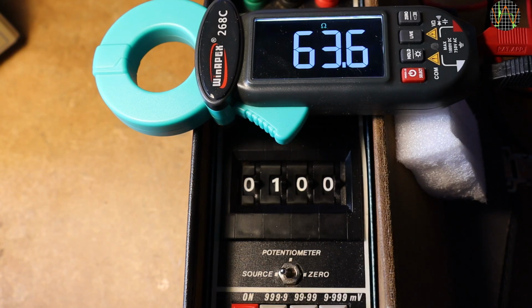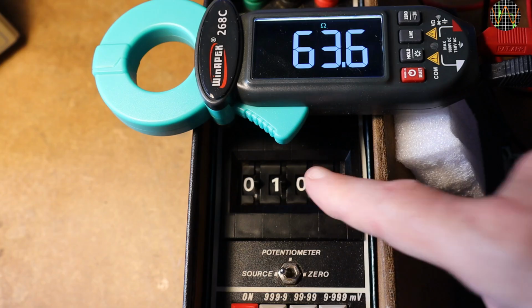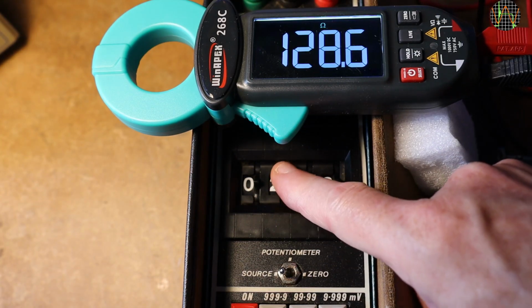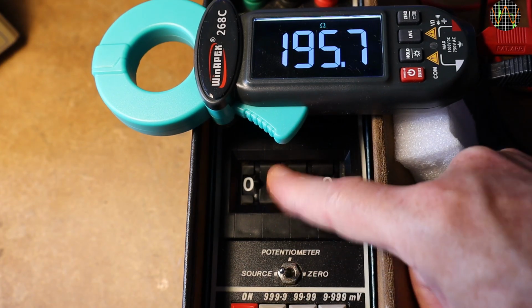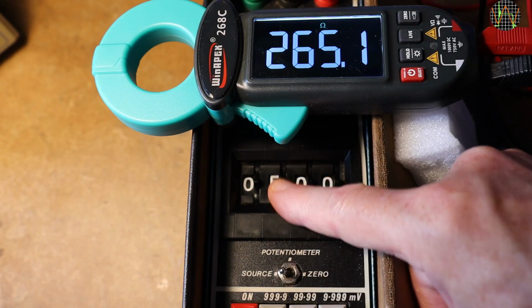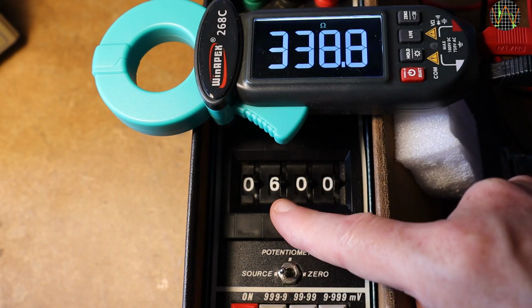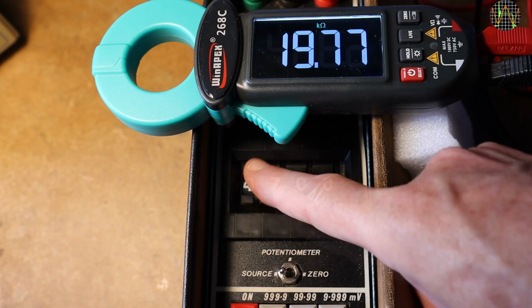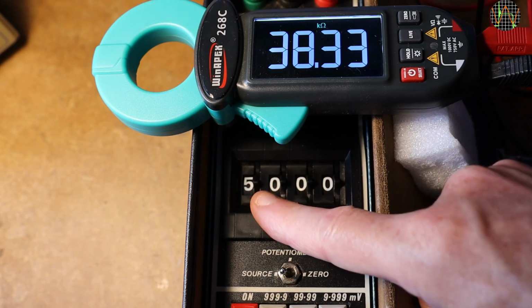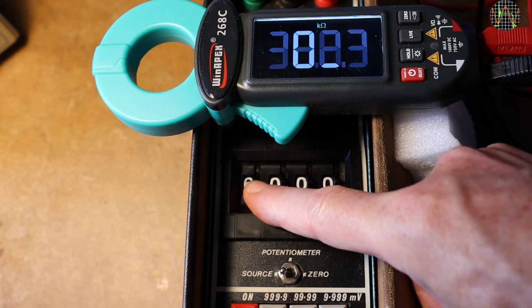Some strange ohm value appears and, increasingly, the input voltage just changed the ohms value. What happens is that the meter pumps out its own voltage in resistance mode, which interferes with the voltage coming from my calibrator, and it's interpreted as a resistance. This is not good for the meter and not good for the source, which in this case is my calibrator.